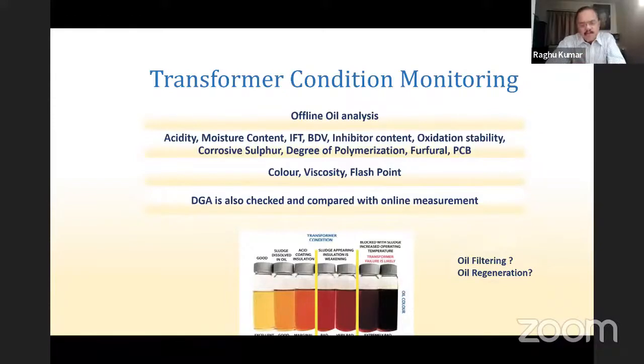See, color is something which you can easily identify. These are samples of oil with different colors from good to bad. The good oil will look like that, and the worst oil is looking like this. Why this oil color changes is due to sludge formation. And once the sludge is there, the cooling efficiency is reduced drastically.